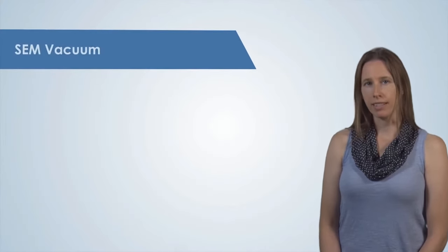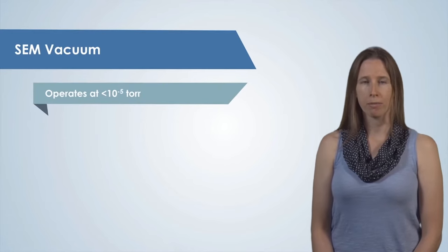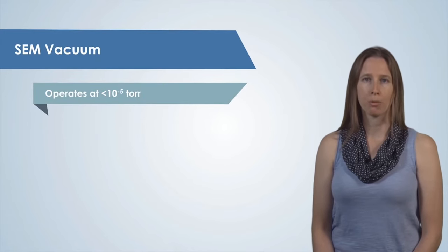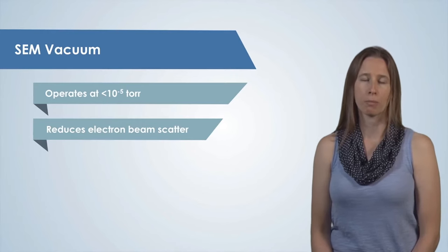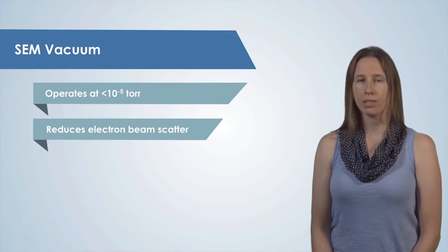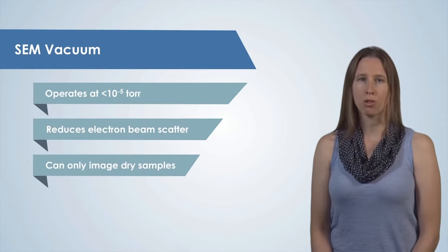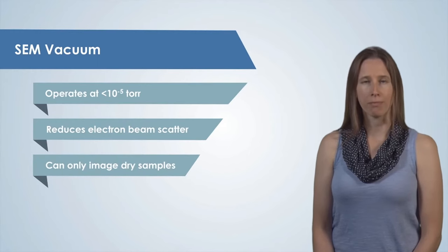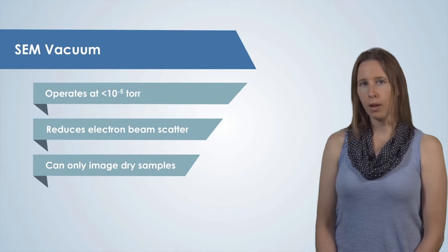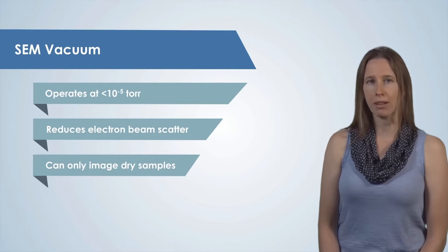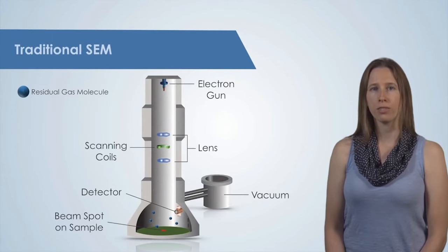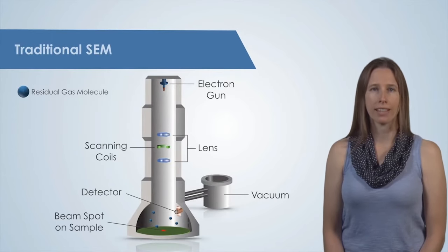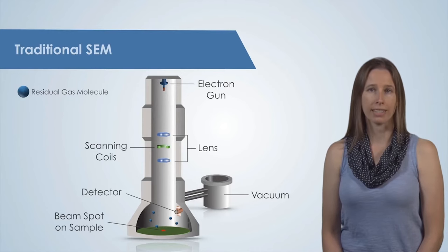In a typical SEM, vacuum is required because the electrons that we use for imaging will scatter off gas molecules and prevent us from focusing the electron beam on the sample. As a result, we can only image dry samples in a typical SEM. If we want to look at wet samples, we need to dry them out first, and this often distorts their shape.